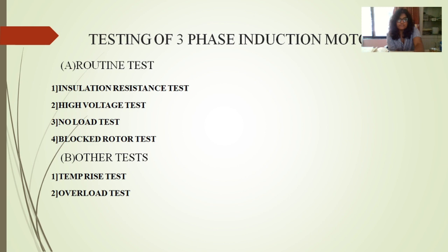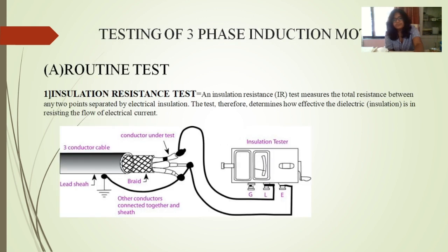Testing of three-phase induction motor. First is the routine test, as we discussed earlier, in which there is an insulation resistance test, a high voltage test, no load test, and a blocked rotor test. And the other tests comprise the temperature rise test and overload test. So first, getting into the routine test, the first sub part is the insulation resistance test.